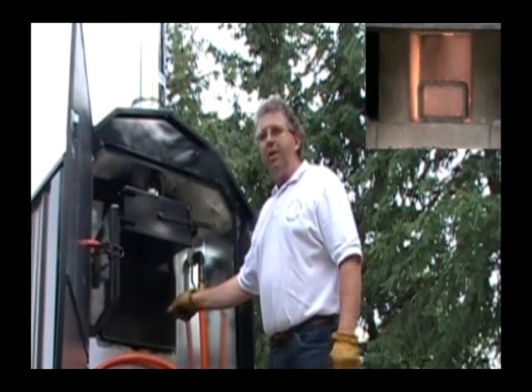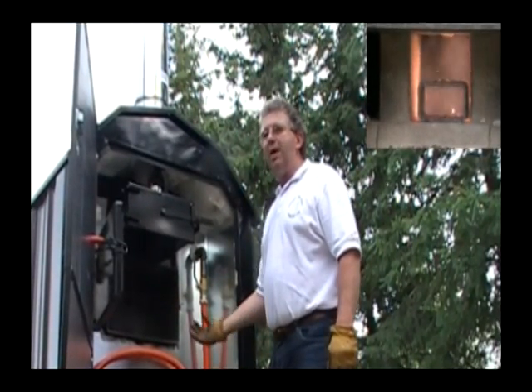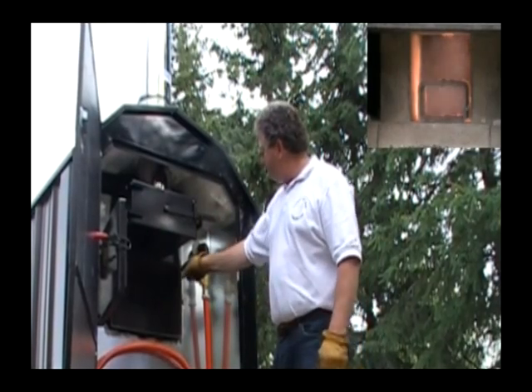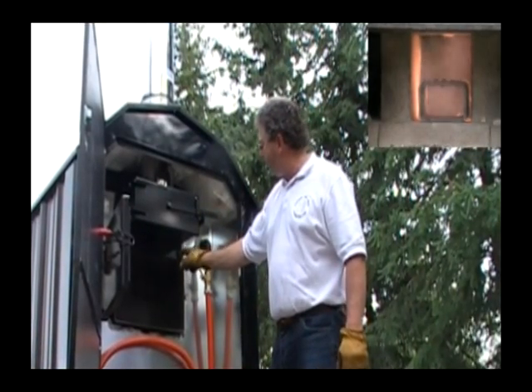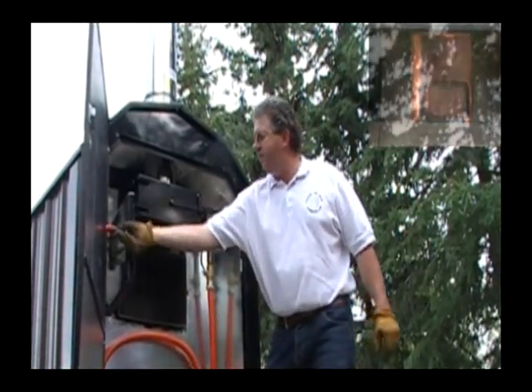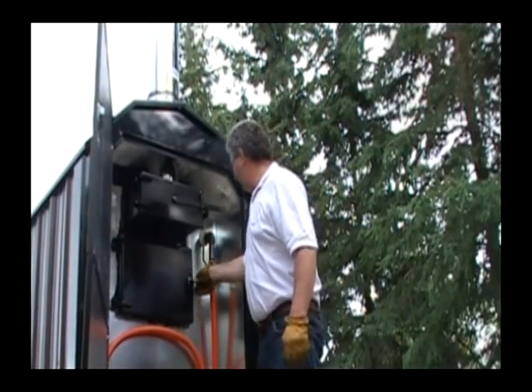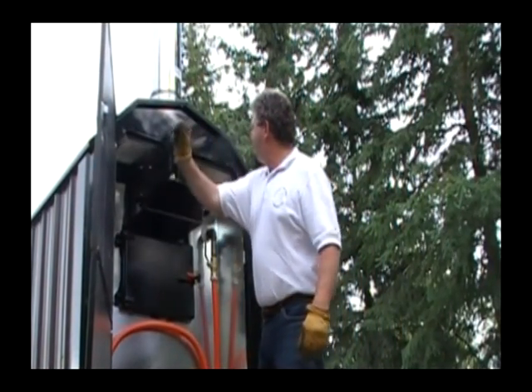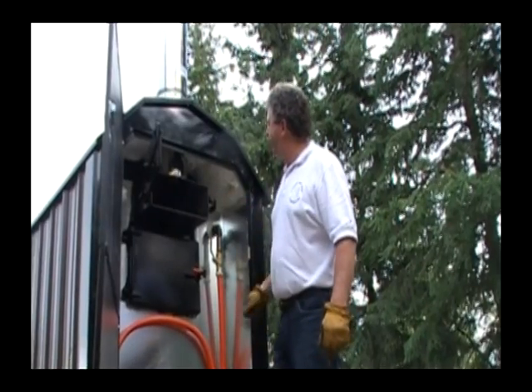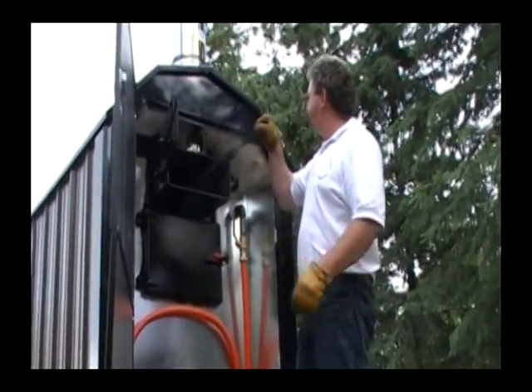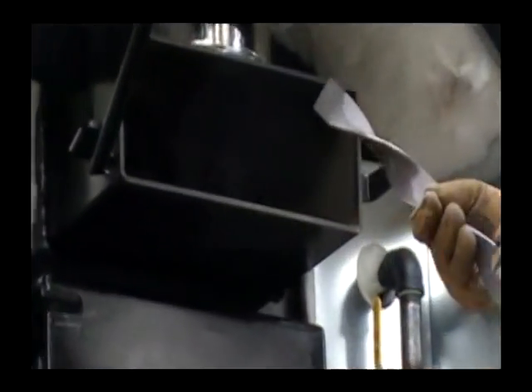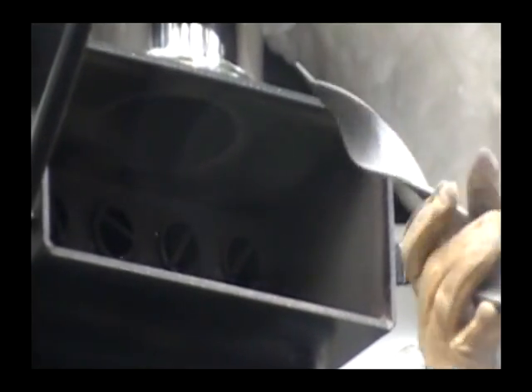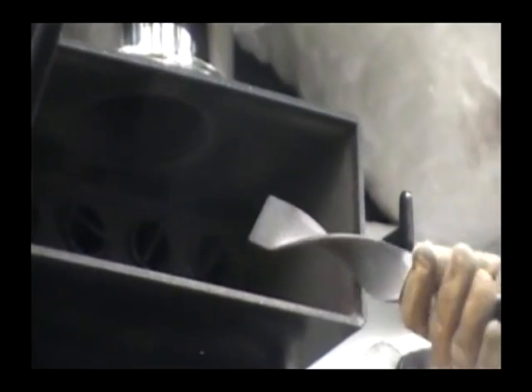A lot of our competitors will end their heat exchanger at something like that and go into the stack. We do a 90-degree turn and go to the front of the stove through these 10 tubes with the turbulators in it. At the front of the stove, we turn around and come to the back, and we have another 10 tubes with turbulators in it. 1.5 inches in size. There's only going to be dust up here. It's very easy to brush the dust out.